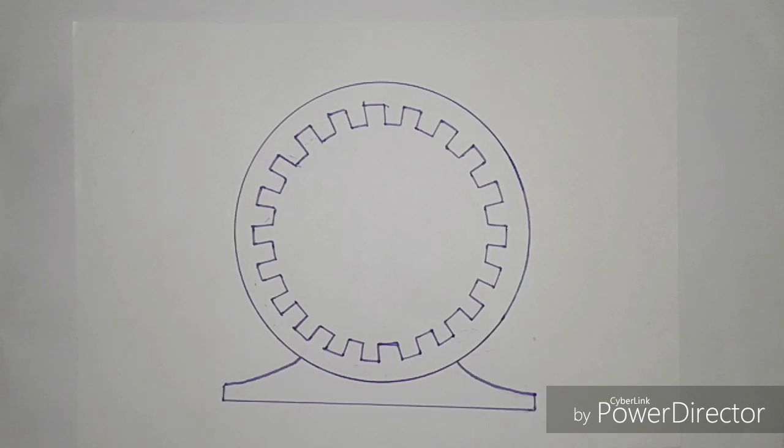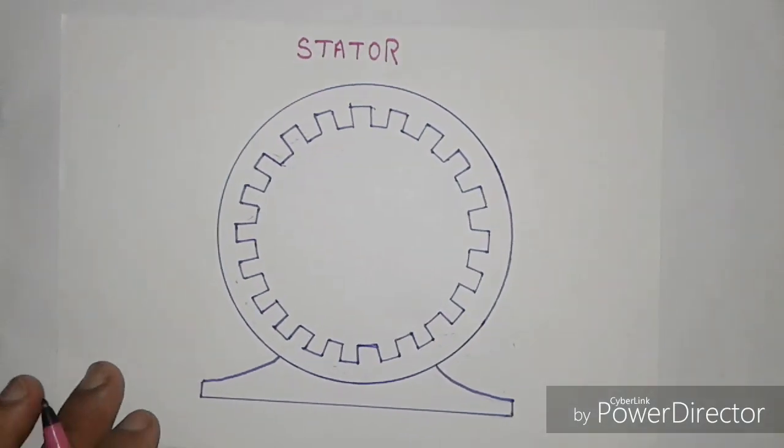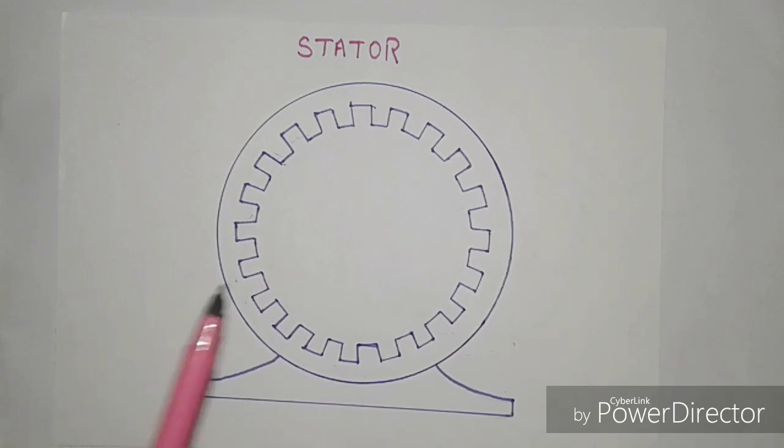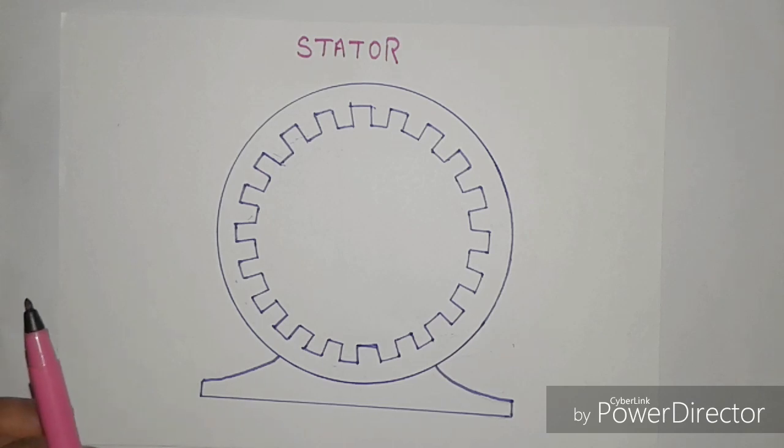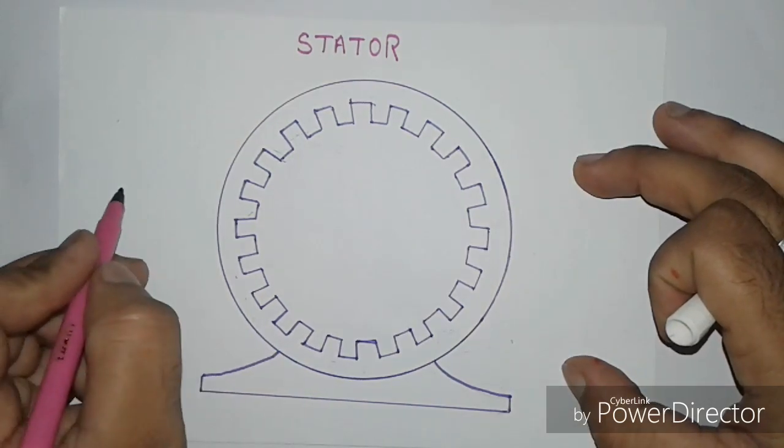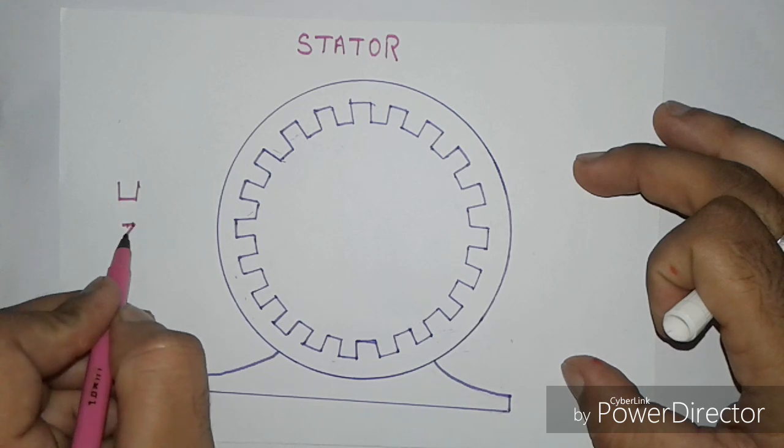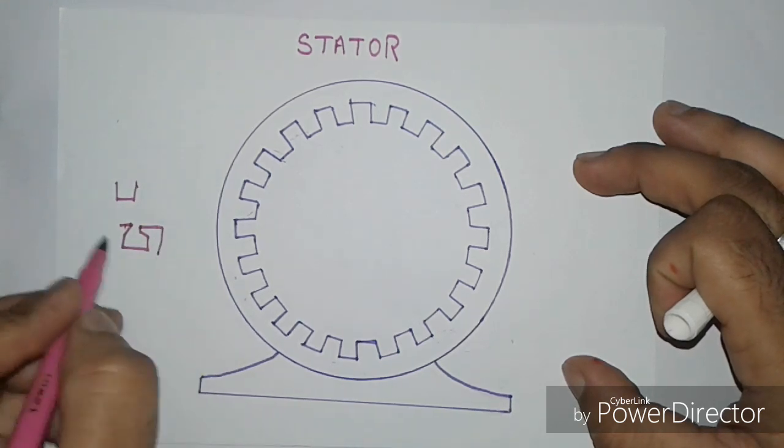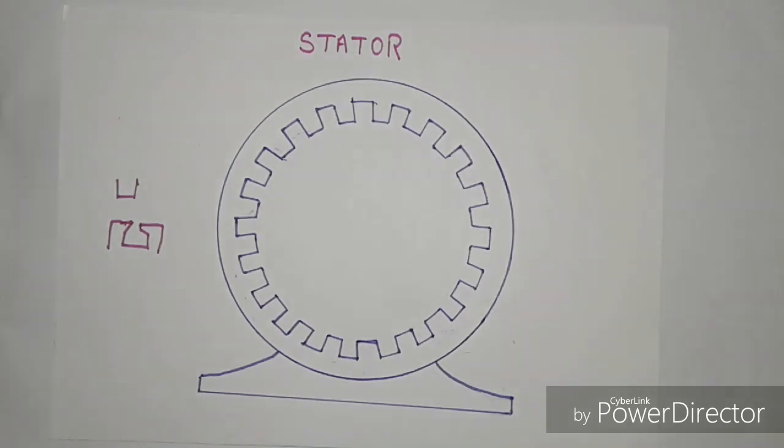The stator is a stationary part of an alternator and it is made up by joining thin laminated silicon steel strips together. In the inner part of the stator, some slots are cut. These slots are either open type or semi-closed type in which armature winding is placed. The stator is welded or screwed to the frame to prevent vibration.